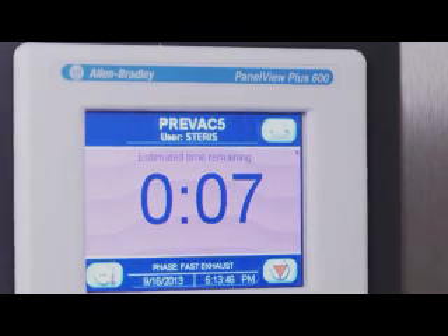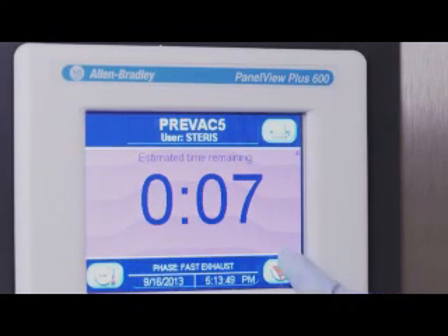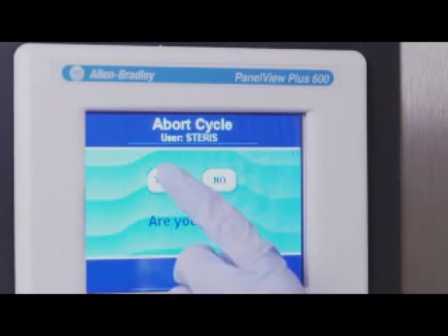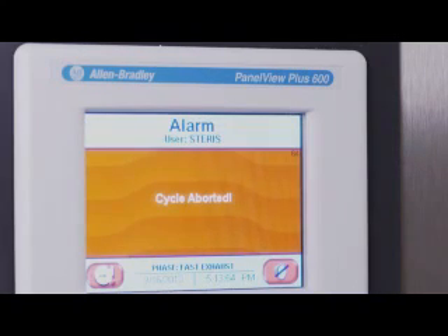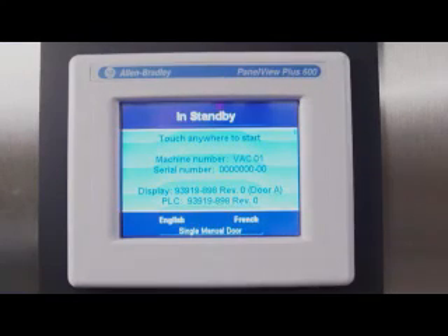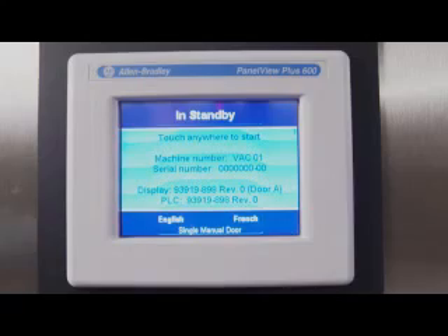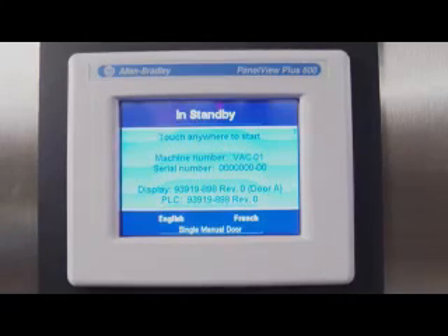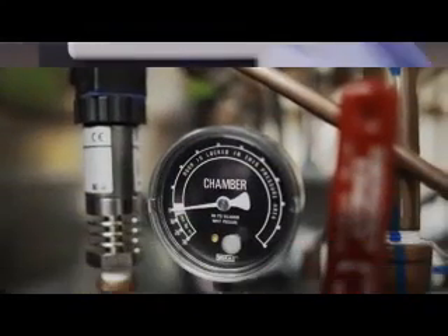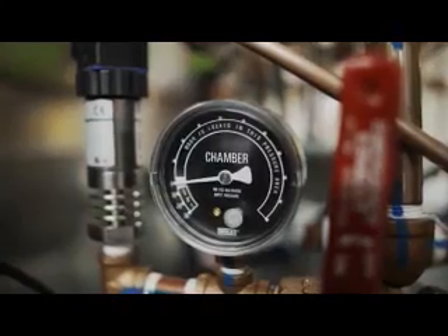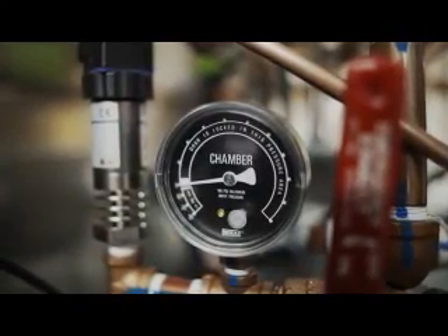Occasionally, you might need to end a cycle before it is complete. For this, you use the Abort touchscreen button, represented by the red triangle. Pressing Abort causes the sterilizer to stop and return to the standby state. Once the sterilizer has returned to a standby state, the door seal deactivates and the control returns to standby mode. In the case of any aborted cycle, be sure to check the chamber pressure gauge prior to opening the door.